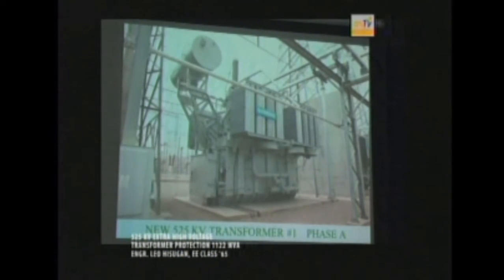You can see how beautiful the 500 kV transmission line tower is. Normally, this is a bundled conductor each phase, like 2 number 2300 kcm conductor. Could be an ACSR or ACSS, you know, depending on the design. Here we have seen the single-phase transformer from all the way from Siemens, I think this is in Austria or Germany, brought in from those countries. This is a single-phase unit only, and Siemens. So, for example, a phase A, only A phase, you know.